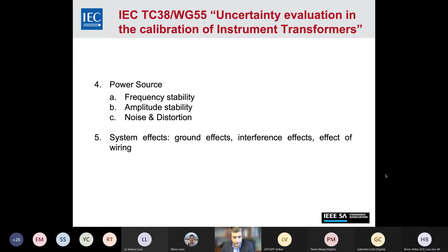Last but not least, the processing. The software used can be a source of uncertainty and can propagate the effects of uncertainty arising outside of it. That's why we studied a lot which software and method to use for extracting the amplitude and phase errors. We considered the leakage effect, the mathematical expression used for evaluation, and aliasing problems, in particular for the Rogowski coil, where amplification of noise in frequency can be dangerous.